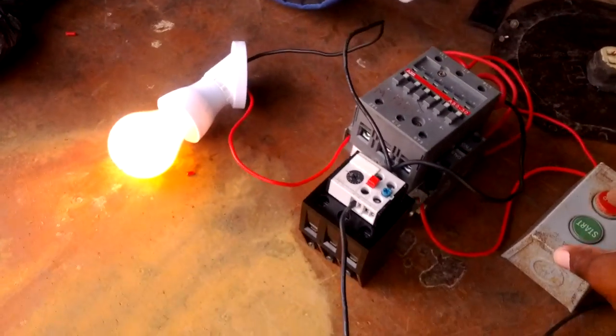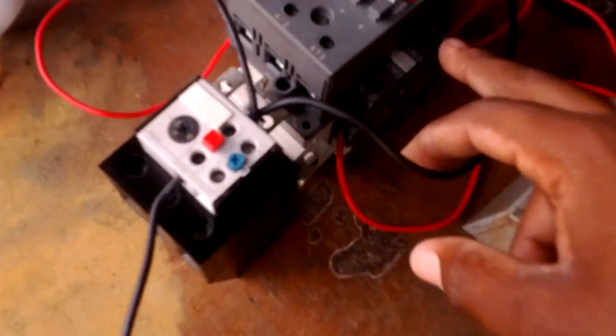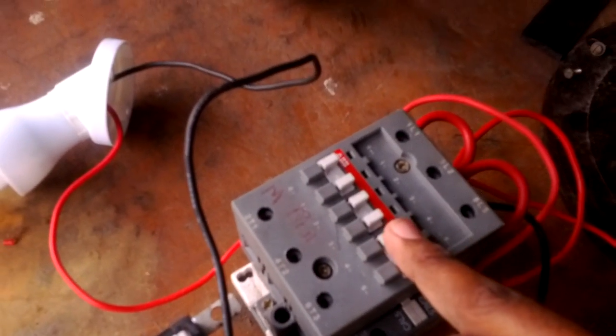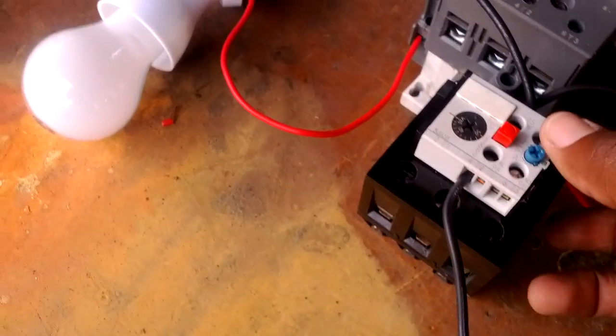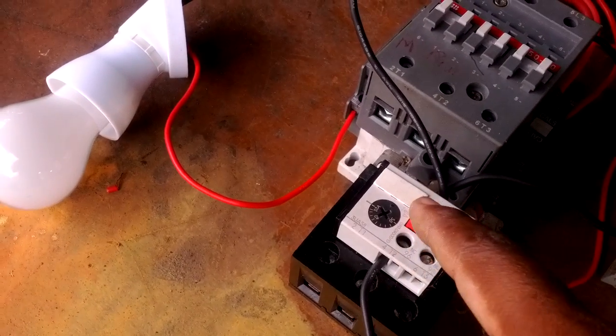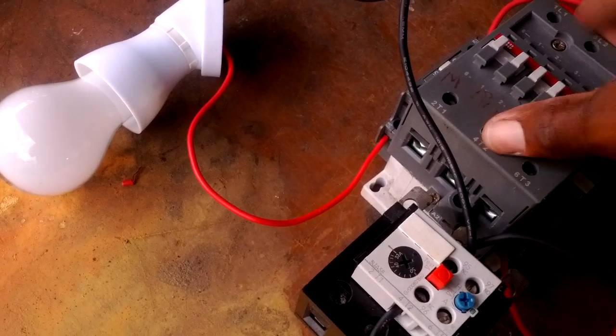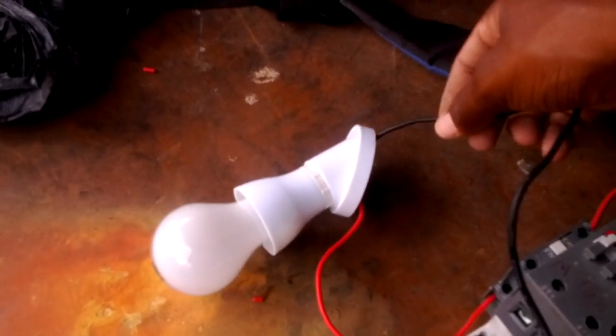So just start and stop. As you see, my auxiliaries are out, the coil is out. The coil controls the auxiliary, keep that in mind. My neutral goes through my overload, so in case the motor is overloading, it breaks the continuity for the neutral. The contactor slams out, the coil is de-energized, and it breaks off the light.